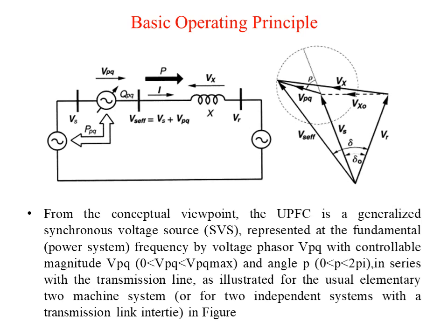The UPFC is connected in series with the transmission line as illustrated for an elementary two-machine system, or for two independent systems with a transmission line inter-tie as shown in the figure. The voltage Vpq is controllable from 0 to its maximum value Vpq_max. As seen earlier, the term 'unified' means it controls voltage, impedance, and phase angle simultaneously, so when we control the voltage the phase angle also changes.